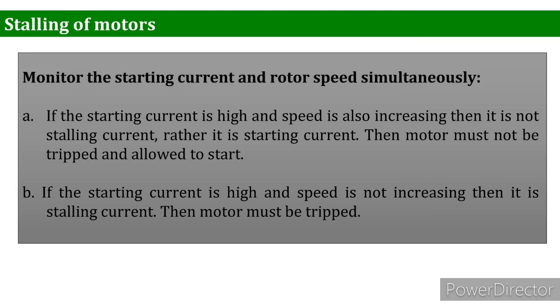So it is important to understand what the starting current is and what the stalling current is. In the first condition, if the starting current is going higher and the speed is also increasing, you don't have to worry about it. It is just a starting current, not a stalling current. But in the second condition, if the starting current is high and the speed is not increasing, then it is a sign of a serious worry. That means the current is increasing but the speed is not, so it is a stalling current. In this case, to avoid damage, the motor needs to be tripped.